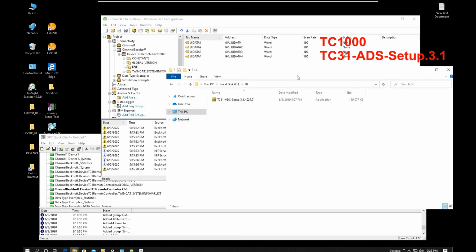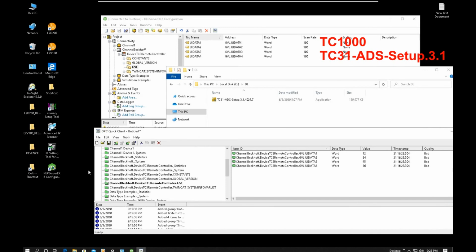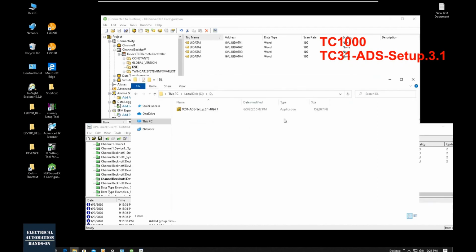And if this KEPServer is installed together with TwinCAT3, when you install the TwinCAT3, it already installs this ADS, so you will not find this problem. But once you use one fresh laptop that did not install the TwinCAT3, and you install the KEPServerEX software, this software doesn't have this ADS driver inside. That's why we need to install this. Okay, we double click and install that.